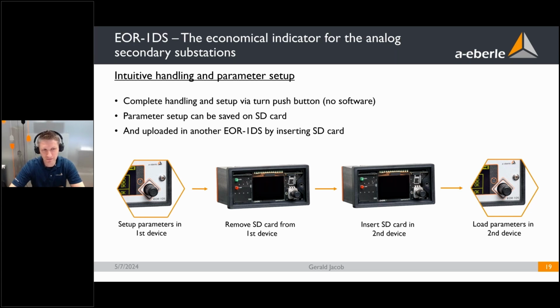There's no software available for this device. All the parameters have to be set on the device itself with this turn push button on the front. What you can do is you can clone or copy this parameter setup of one device to a second device. So you set up the complete device, remove the SD card from the first device, insert it into the second device, and then load the complete parameter setup in the second device.